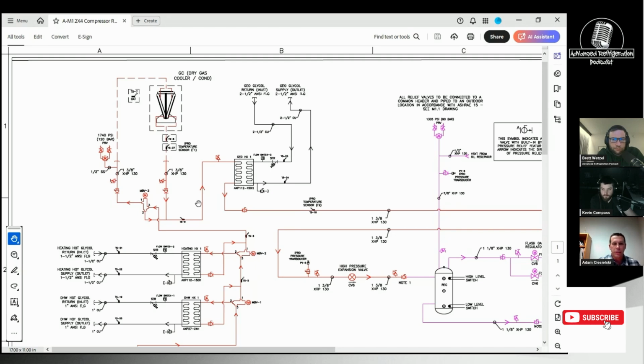The most important thing is, I've seen situations when it gets cold out and the fans are running at 0 speed and maybe cycling off from 0 to 5% or whatever the current setup is. Even that is not enough, and the temperatures start dropping. Eventually, your receiver pressure starts dropping. And then you eventually lose your medium temp, and the rack just cascades and falls down.